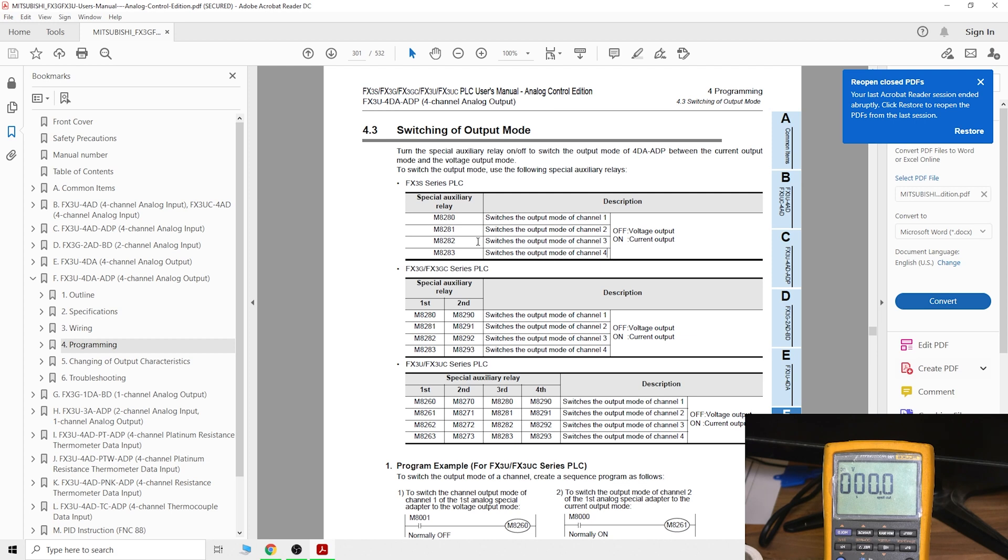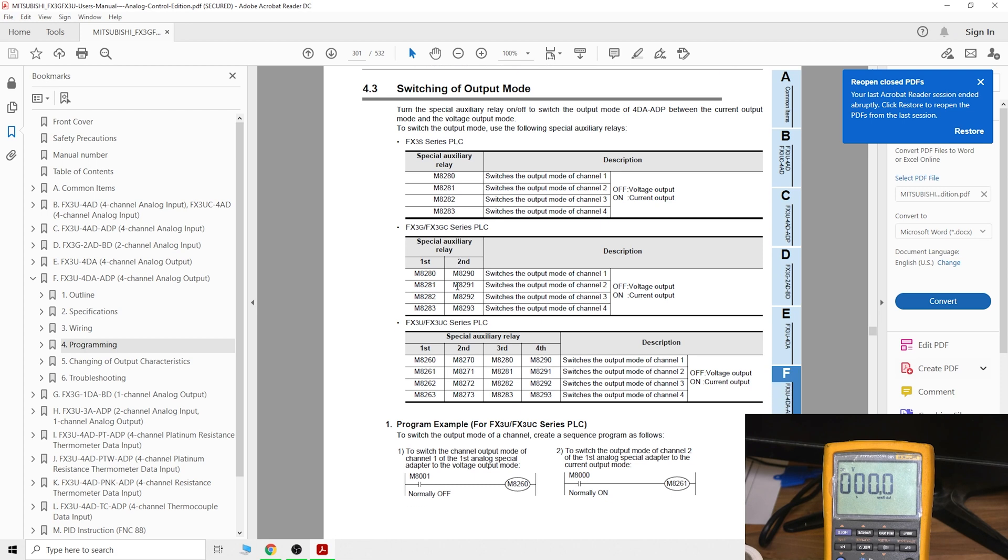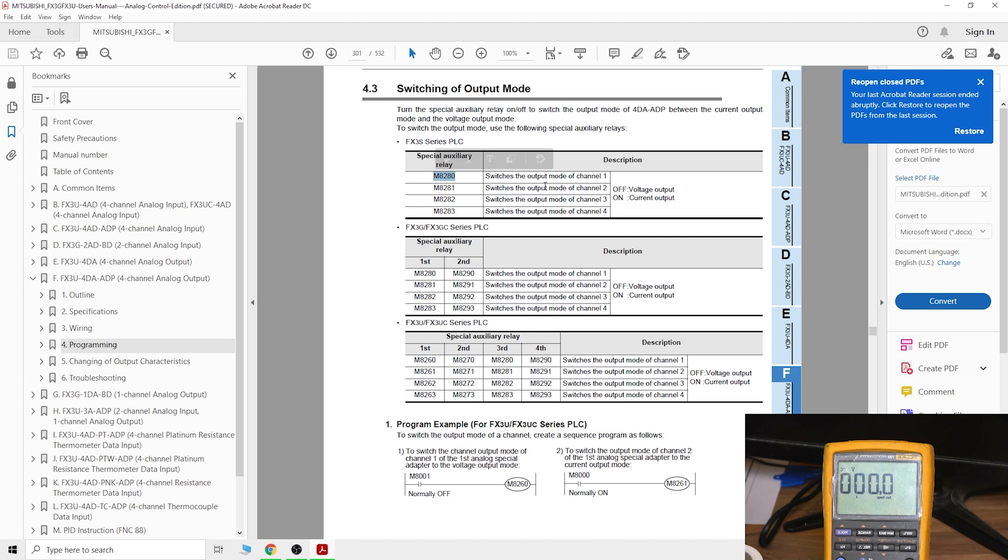Here we go. For switching mode for switching to output modes, you can see the same auxiliary contacts have been assigned to the digital analog output card. It's the same switches as for the analog input card. If you want to use both analog input and output, you won't be able to do it because you can only add one card to FX3S PLC.